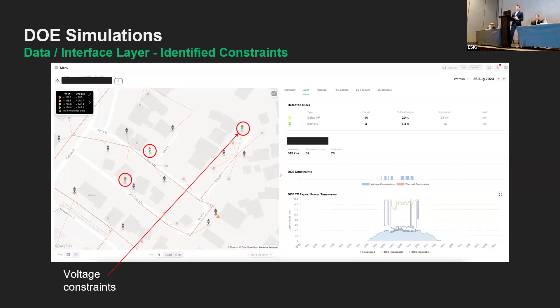This screenshot here is really just showing where those circles are. The upper arrows in red show where there were measured voltage excursions, and the graph down the bottom, at a distribution substation level, which I'll go to now, shows what the DOE did in that situation. This is at an aggregate level. You can see the tan and purple lines are the DOE's binding to avoid that voltage constraint. And then you can see the amount of curtailed energy between the blue and those shaded bands for each spin.